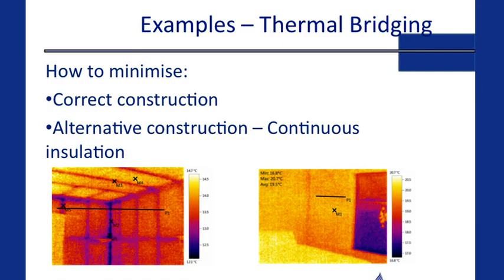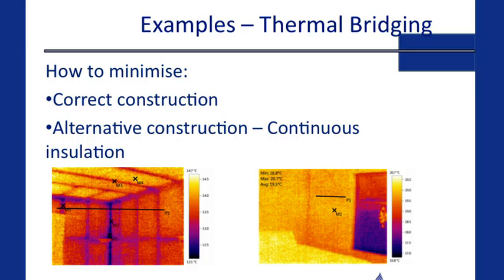Following on from Andrew's talk about thermal bridging — in the image on the left, you can see a bunch of cold dark lines. Those are the structural members of the roof and the walls. That provides the least path of resistance, so you lose a lot of heat through that wall. To avoid that, you use correct construction such as thermal breaks, or alternative constructions like continuous insulation — things like structurally insulated panels. The image on the right-hand side is of a structurally insulated panel. There are no structural members, so there's no bridging, giving you a consistent layer of insulation which also provides a consistent air barrier.